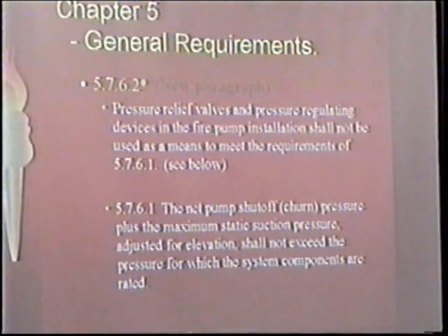But they do allow you to put a relief valve in an installation where they have a variable speed control. They require it, but it's not allowed to open at constant speed operation. It's only allowed to open should the VFD somehow get hung up so it goes over the rated speed. So if you currently have those inline pressure reducers, you got to clean those. That is not retroactive. To my knowledge, it is not retroactive.